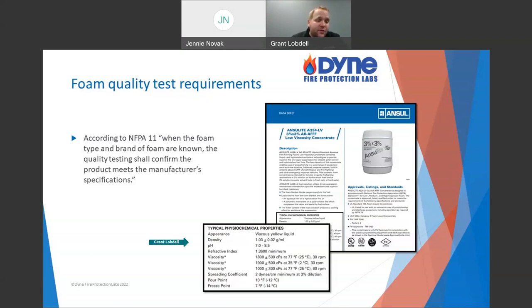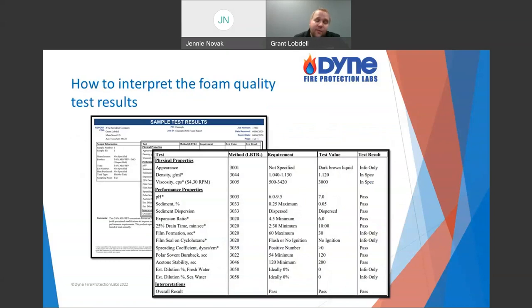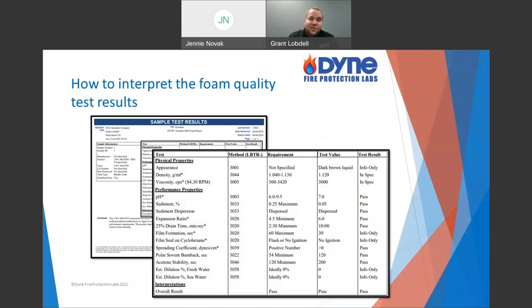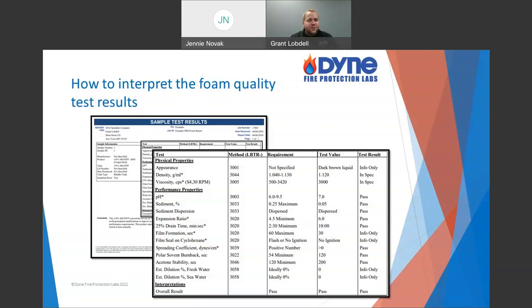Once we have all the results, we compare them to the manufacturer-specified properties. Putting it all together: why do we do it? We want to ensure continued performance, and we do it because it's required — annually per NFPA 11 and NFPA 25. What tests do we do? Expansion and drain time for sure, film formation for film-forming foams, and a variety of physical properties. You get a report like what's shown on screen — just an example with sample results to demonstrate what it may look like. Appearance is info-only; for instance, if you have a protein foam that's supposed to be dark brown and you have something blue, that should tell you you probably don't have what you thought.